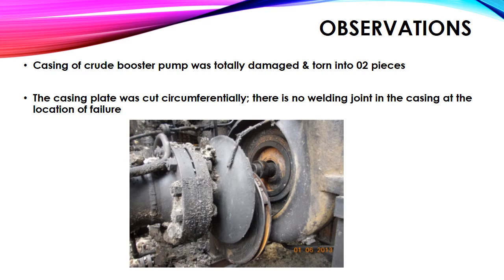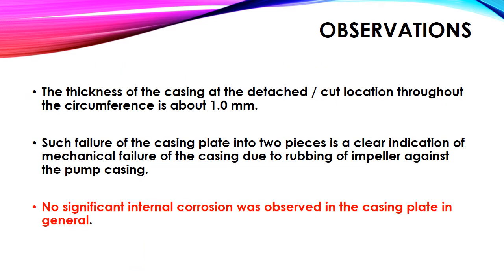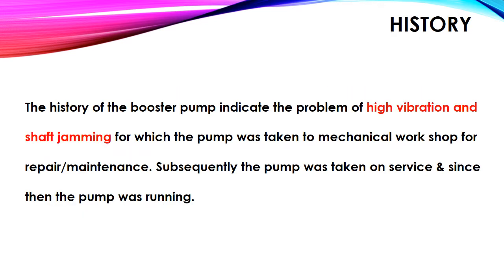The casing of the booster pump was totally damaged and torn into two pieces. The casing plate was cut circumferentially. There is no welding joint in the casing at the location of failure. See this picture. Thickness of the casing at the detached or cut location throughout the circumference is about 1 mm. Such failure of the casing plate into two pieces is a clear indication of mechanical failure of the casing due to rubbing of the impeller against the pump casing. No significant internal corrosion was observed in the casing plate in general.